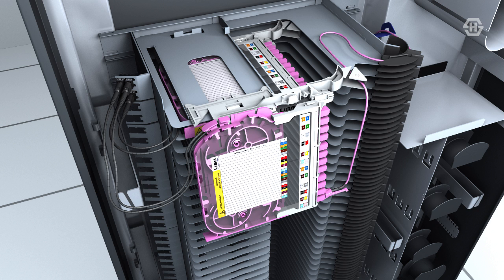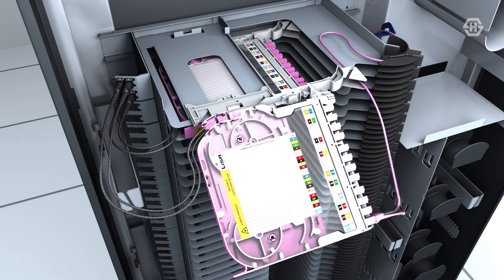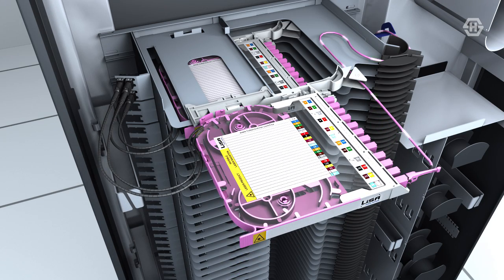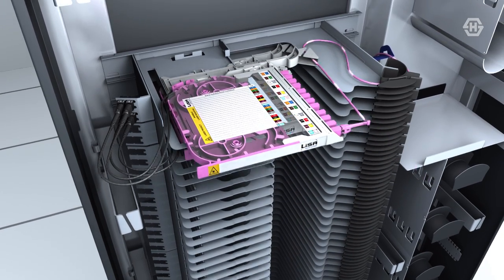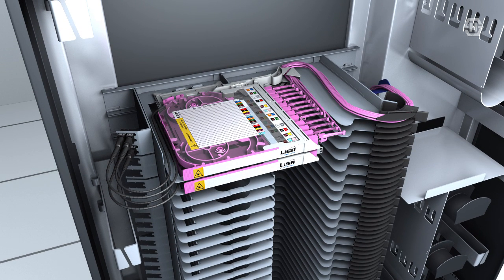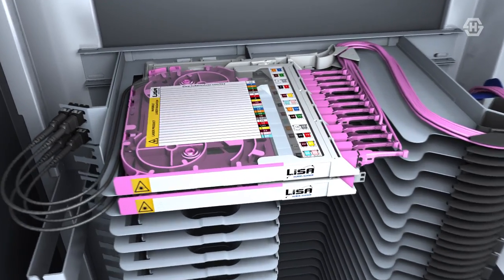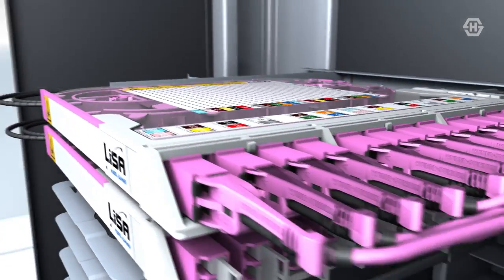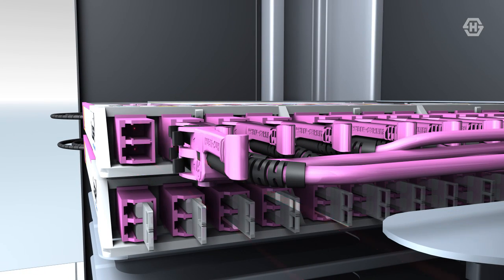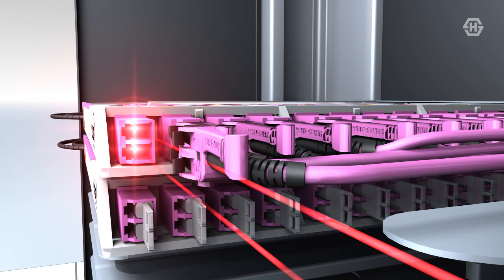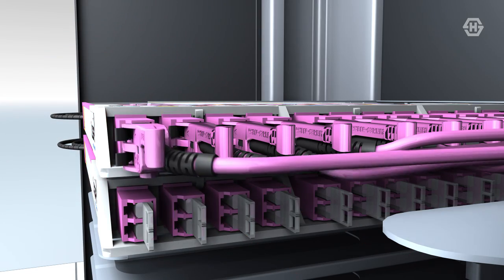Because the Lisa fiber tray has side-facing connectors and an integrated service loop, it's possible to pull out or push in the tray even when live fibers are connected. This isn't possible with standard front-facing systems because generally there is no slack management of the patch cords. The side-facing design also has benefits to the user because even when they are patching at head height, they are not exposed to harmful light exposure from live unmated connectors.